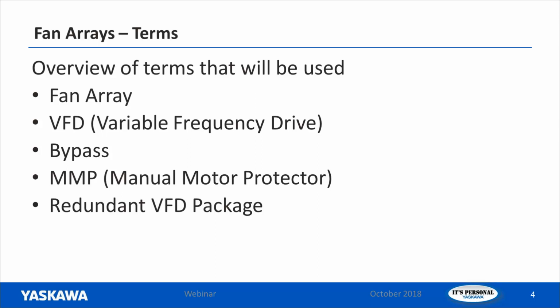Next will be a bypass, and that is as it pertains to using a VFD. So you could be running a motor with a VFD. The bypass option would be having contactors to redirect the line power around the VFD, going directly to the motor to run it right across the line. Next will be MMP, and that stands for manual motor protector. This is like a combination overload and motor circuit protector with a switch on it, and I'll show you what that looks like a little bit later.